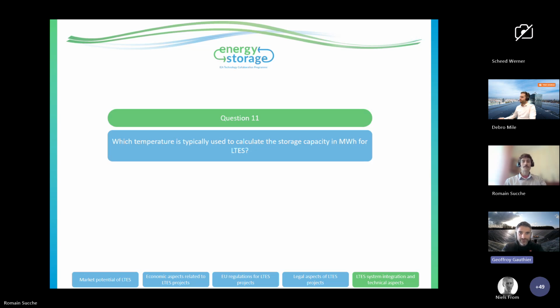This very much differs from technology to technology, but I will speak for the two technologies I know best: pit and tank thermal energy storage. For pit thermal energy storage, the temperatures considered usually go up to 90 degrees, and some very recent developments allow this to be up to 95 degrees, but not higher. For tank thermal energy storage, the typical maximum temperature would be just before boiling, so about 97 degrees Celsius, accounting for the nucleation of water in a tank. So that's about 97 degrees.